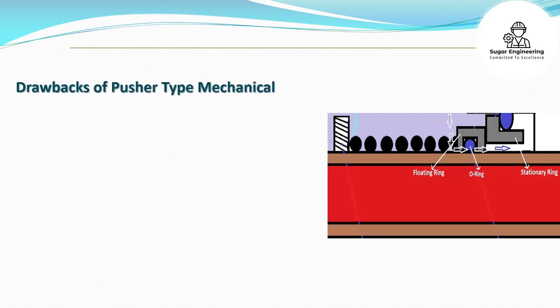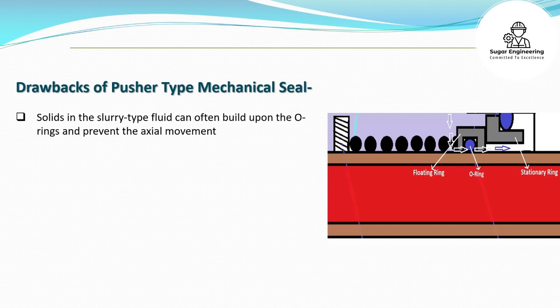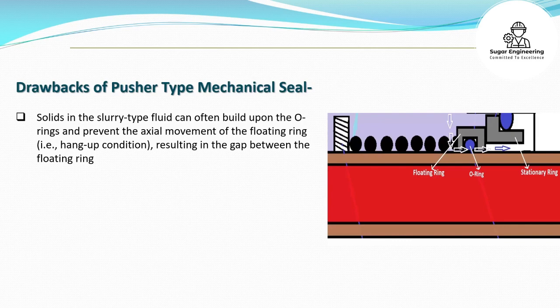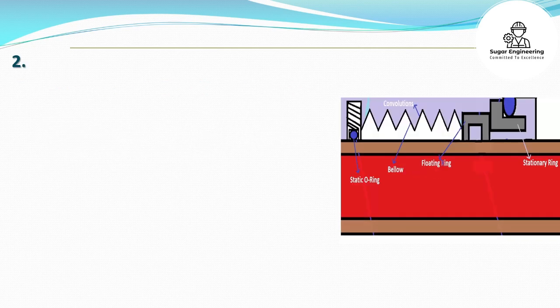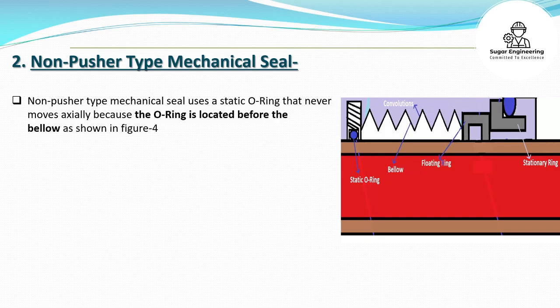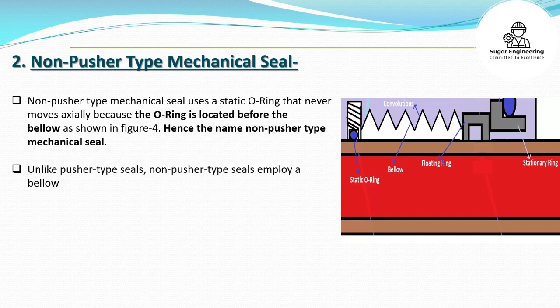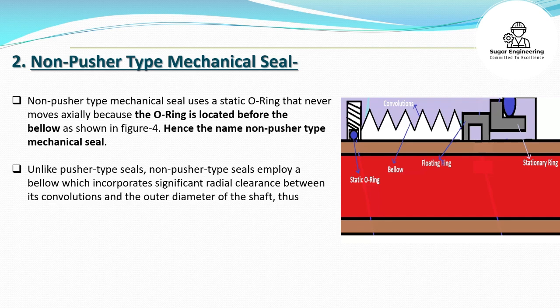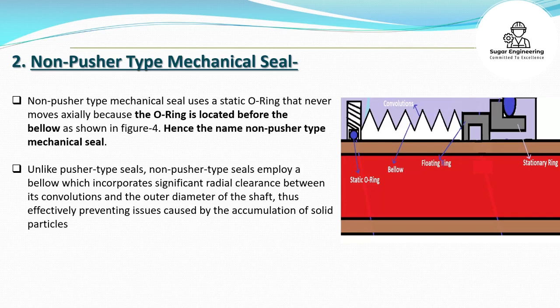Drawbacks of pusher type mechanical seal: Solids in the slurry type fluid can often build up on the O-rings and prevent the axial movement of the floating ring — i.e., a hang-up condition — resulting in a gap between the floating ring and the stationary ring. Non-pusher type mechanical seal: A non-pusher type mechanical seal uses a static O-ring that never moves axially, because the O-ring is located before the bellows, as shown in Figure 4. Unlike pusher type seals, non-pusher type seals employ a bellows which incorporates significant radial clearance between its convolutions and the outer diameter of the shaft, thus effectively preventing issues caused by the accumulation of solid particles, commonly known as the hang-up problem.